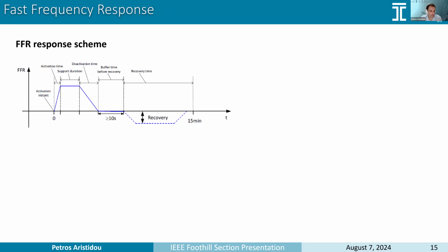In Europe, in many countries, including Cyprus, this is the FFR response scheme that is used. So when a frequency deviation is detected, so there is a trigger frequency, a battery activates. There is an activation time, usually around 500 to 800 milliseconds. Then we have a support duration. It provides some amount of active power to the system in order to shift the nadir to a higher value. And then we have a gradual deactivation time so that the frequency containment reserves can catch this reducing power.